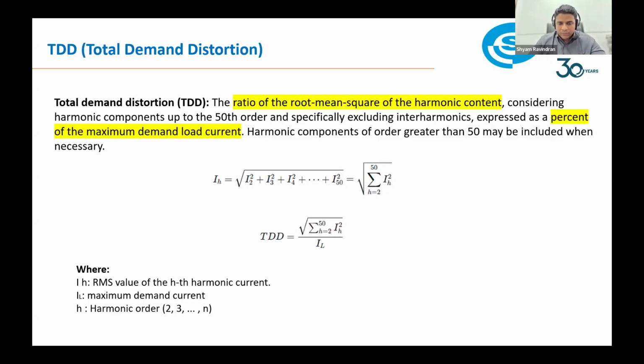Before we start, I personally wanted to start a PQ audit. I will always insist the customer start the company or operations to the maximum that you can do. Because if you take a PQ audit while having an average load which is not very significant, the harmonic distortion running inside the facility will be very, very higher. So we usually insist the customer please give the maximum current.